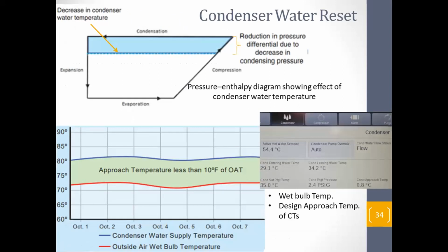Similarly, you can do condenser water reset, by reducing the condenser water temperature leaving the cooling tower. When you reduce the temperature, it will reduce the pressure. When you reduce the pressure, that will make things easier for the compressor. Again, just like the chill water, when you try to reduce the condenser entering temperature, your cooling towers may have to work harder and your condenser water pump may have to work harder. So we have to see the savings from the chiller and the additional consumption of the condenser water pump and the cooling tower, put them together and see whether we are getting a net positive benefit. Right?